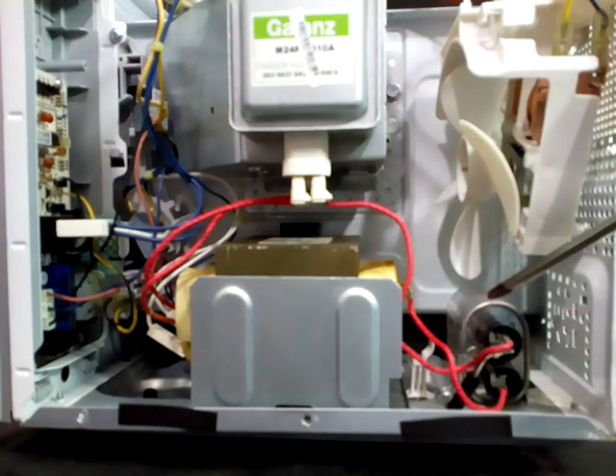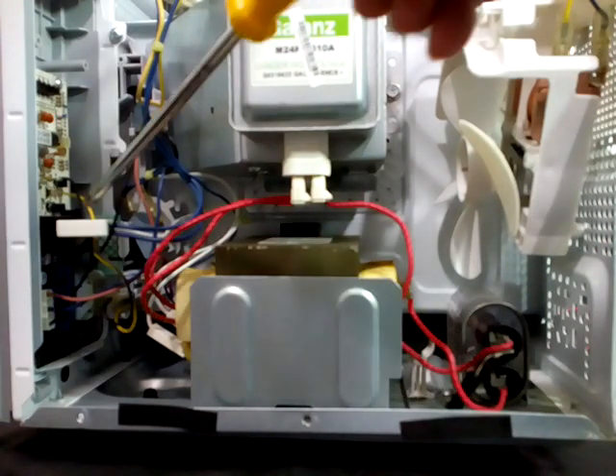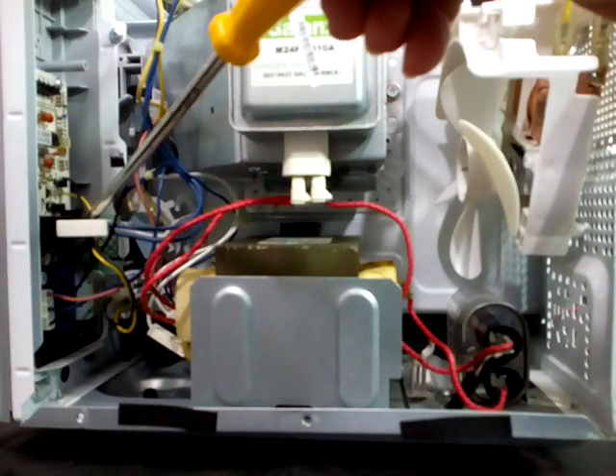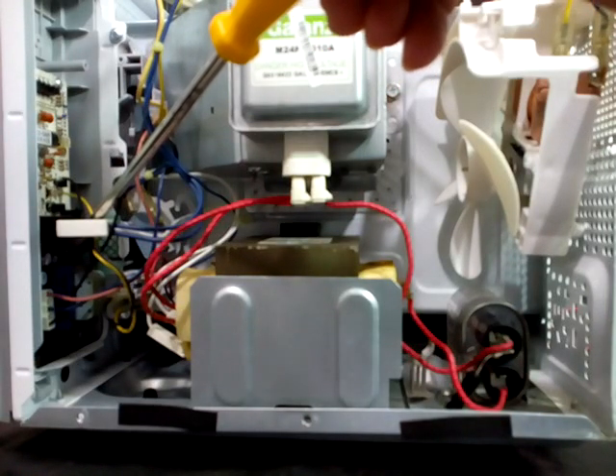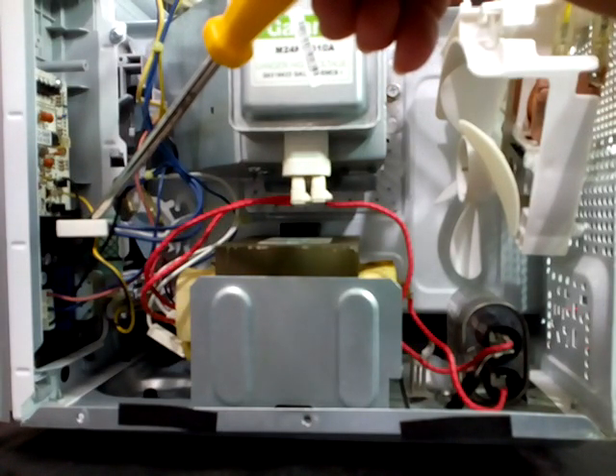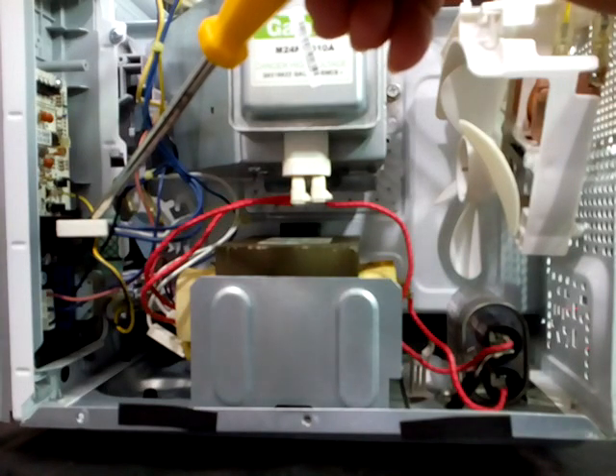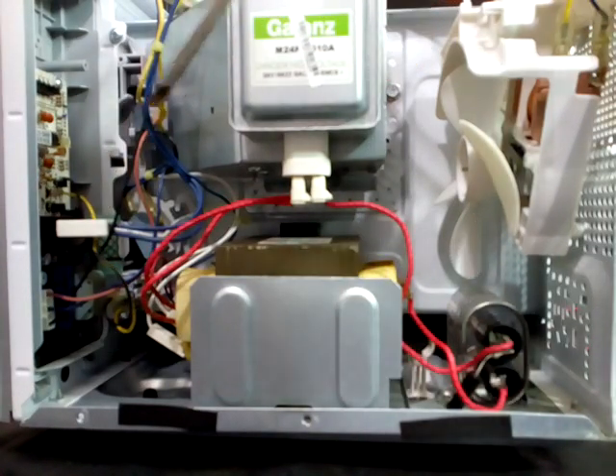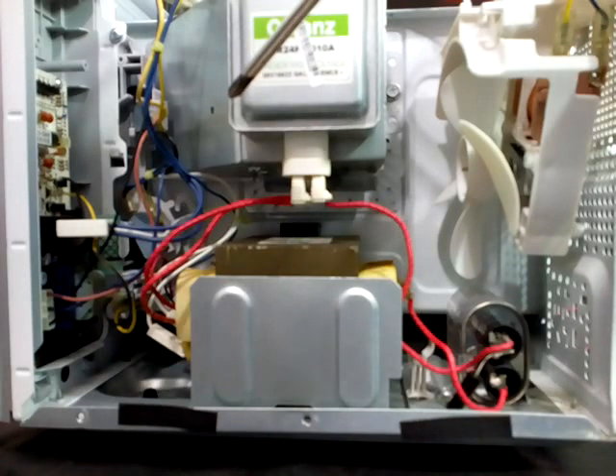Now remember, the control panel has a small fuse to protect the standby power supply, usually less than 1 ampere. So the 20 ampere fuse will always be okay when the panel is short circuited, okay?